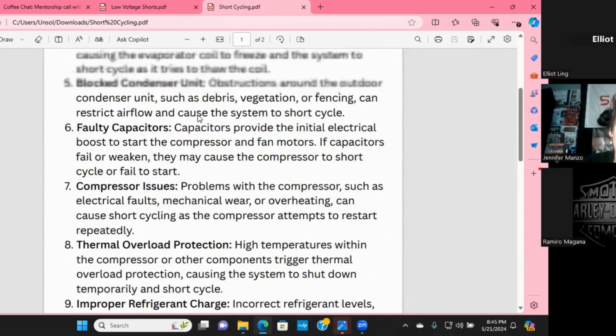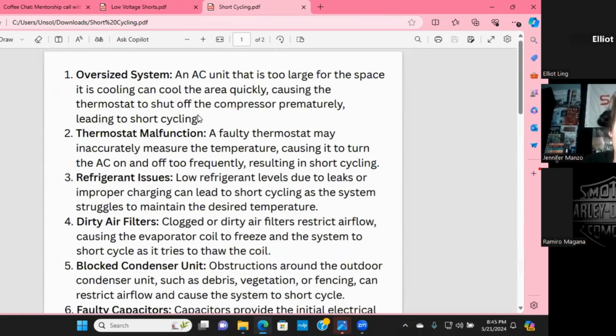Yeah, and overcharging is actually really easy to do. We tend to make fun of each other when it happens, but it really is easy. I can't tell you how many times I've seen a bad TXV mimic undercharge. People think that it's undercharged, so they add refrigerant the whole time. The TXV is doing that Leonardo DiCaprio smug laughing face at them, because the whole time it was a restriction. Okay, so there's that one.